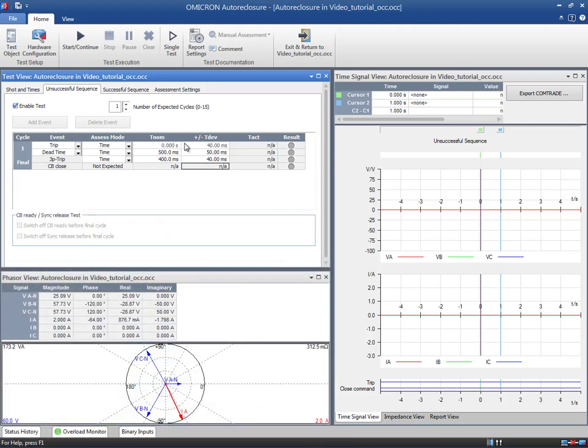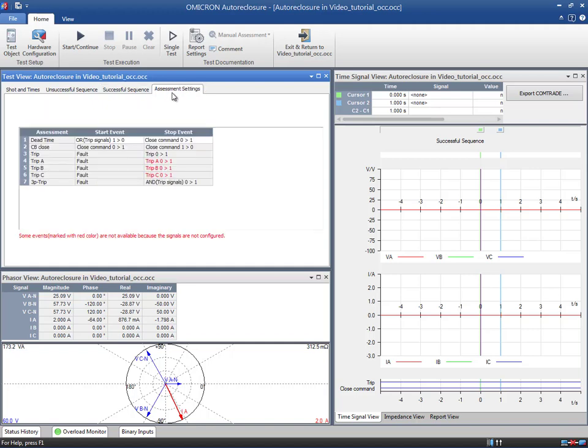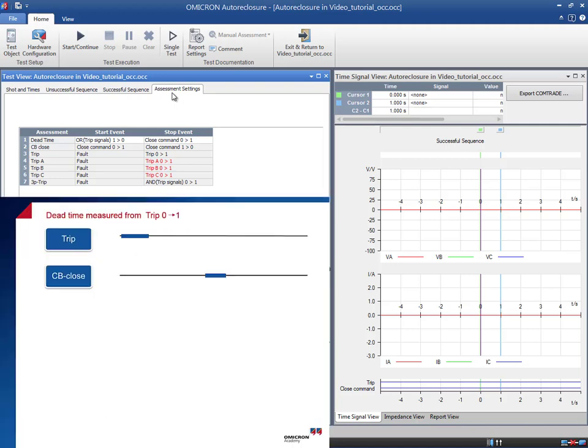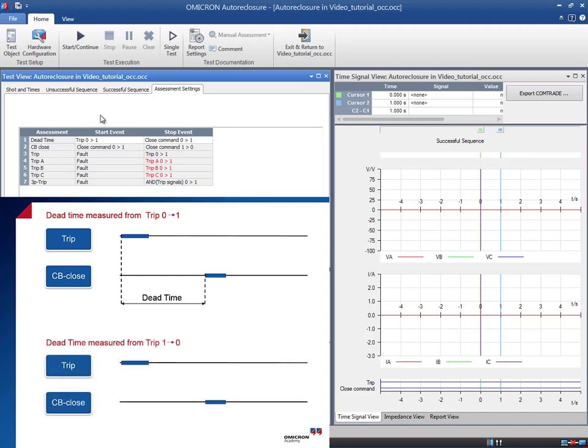If we take a quick look at the Successful Sequence tab, we can see that all the settings are taken from the Unsuccessful Sequence tab automatically. Naturally, this sequence does not include a second trip event. In the Assessment Settings tab, you can enter the start and stop conditions for each measurement. The definition of the dead time might depend on the relay. For some relays, the dead time starts when the trip signal goes from 0 to 1, which suits the relay under test. For some others, it starts when the trip signal goes from 1 to 0. The stop event happens when the close command goes from 0 to 1.